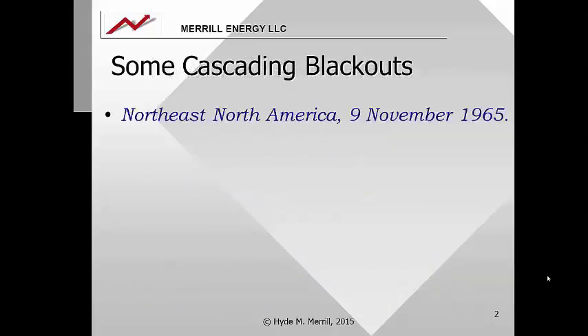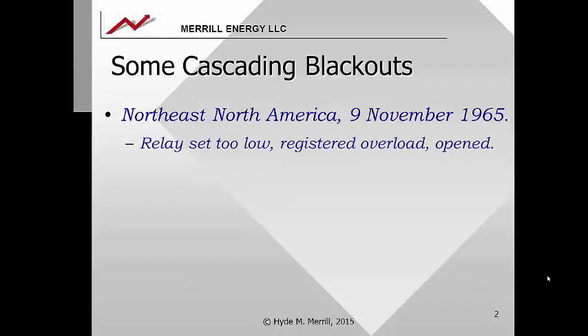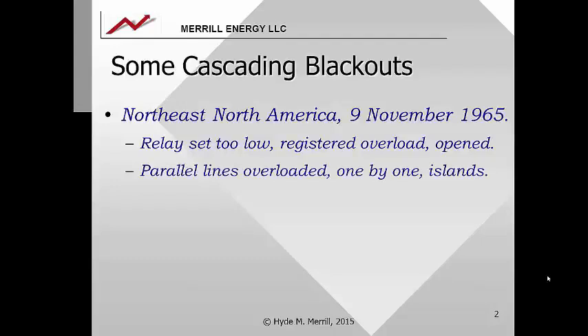The granddaddy of them all was in northeast North America on the 9th of November, 1965. Five transmission lines were carrying power from plants in the Niagara Falls area to Toronto. On one of these lines, a relay was set too low, and although the line wasn't overloaded, the relay detected that it was and took it out of service to protect it. The power that line was carrying was instantaneously redistributed over the remaining four lines. One of those lines overloaded and was also taken out of service automatically. Its power was redistributed over the other three lines, and one by one, within 2.5 seconds, all five lines went out of service.